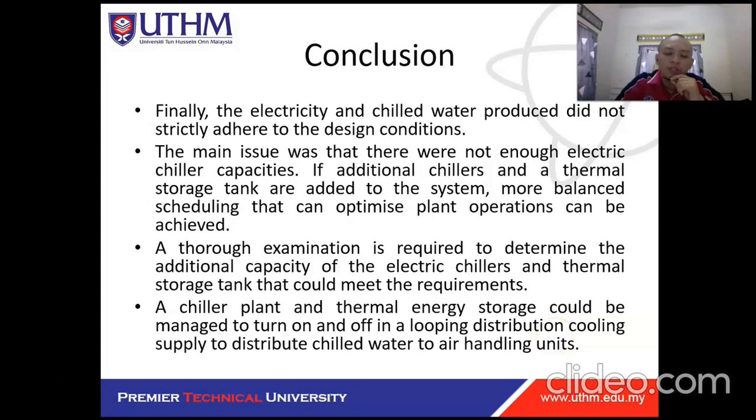So this is the conclusion for experiment number 7. Finally, the electricity and chilled water produced did not strictly adhere to the design condition. The main issue was there were not enough electric chiller capacities.